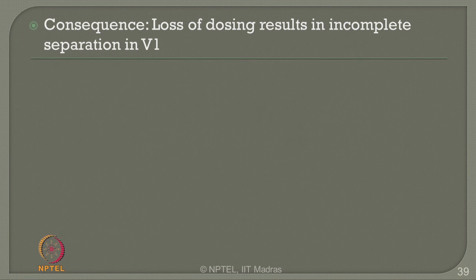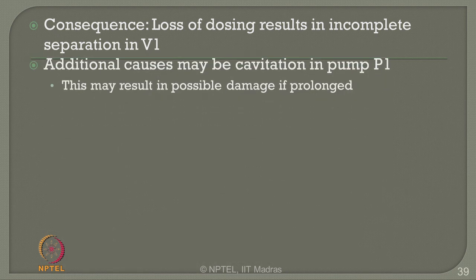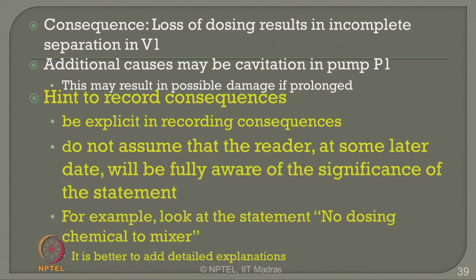Now, let us see the consequences if there is no flow. The consequence can be the loss of dosing, which results in incomplete separation in the tank V1. An additional consequence can be cavitation in the pump P1, because the pump does not receive the required quantity of flow after the strainer S1. Therefore, this may result in possible damage to the pump if it is prolonged.